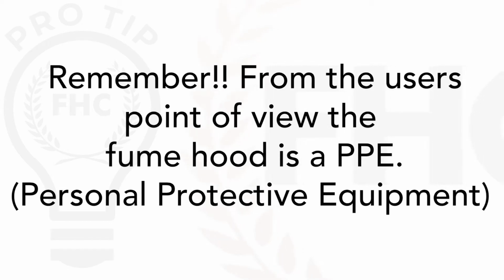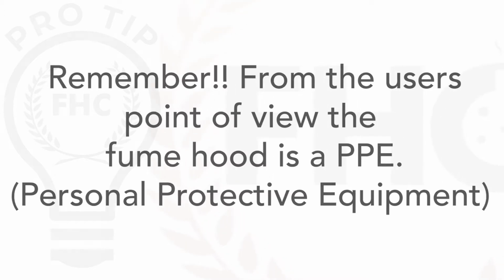Like fires, explosions are all too common. They're harder to predict and harder to prevent. The difference is that the damage is usually concentrated on those using the hood or those nearby the explosion. Remember, from the user's point of view, the fume hood is a PPE. It's also important to understand all the PPEs and safety devices that a fume hood user should be aware of.